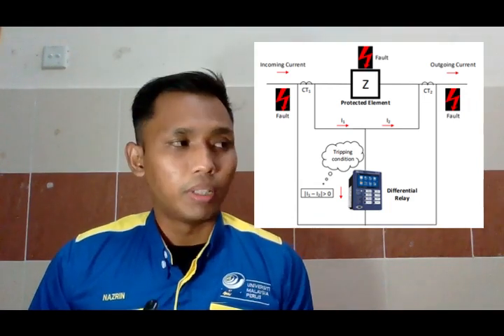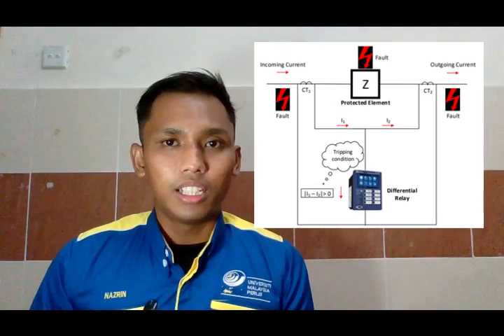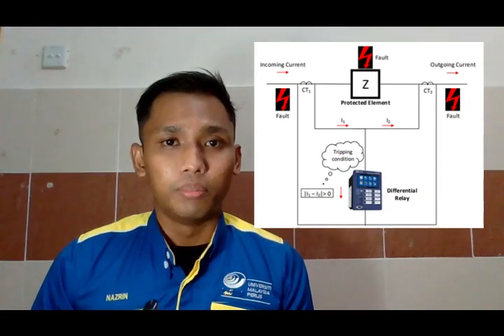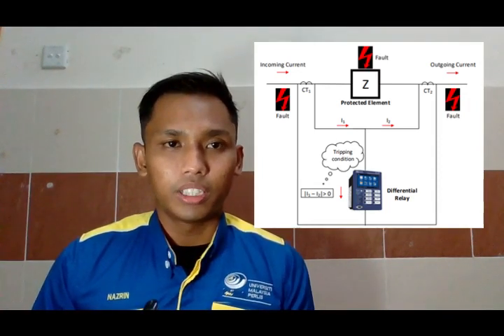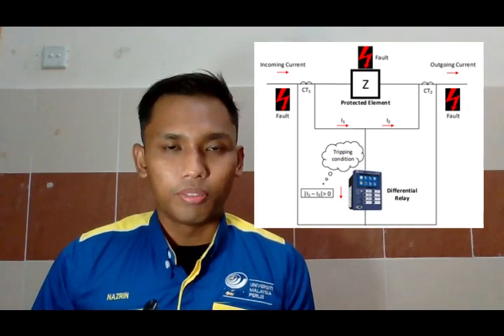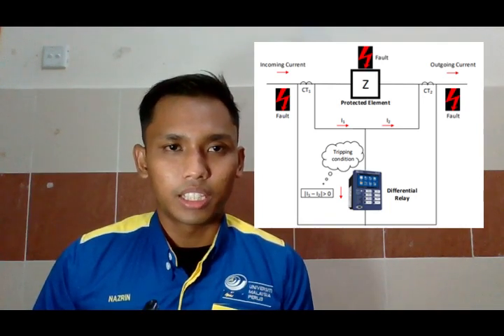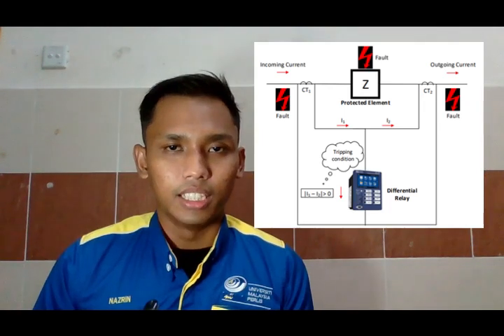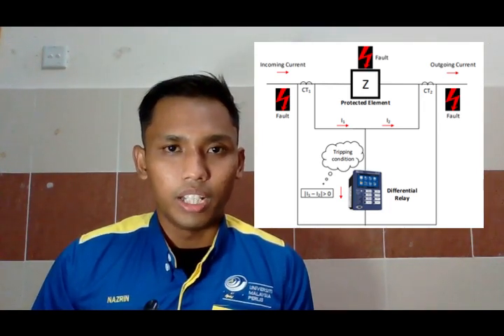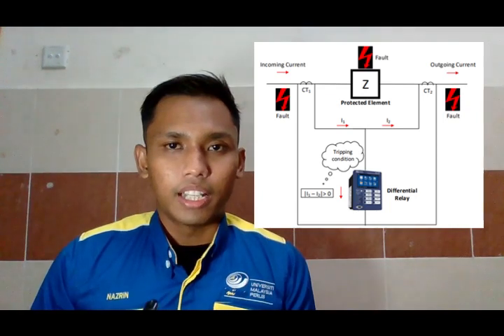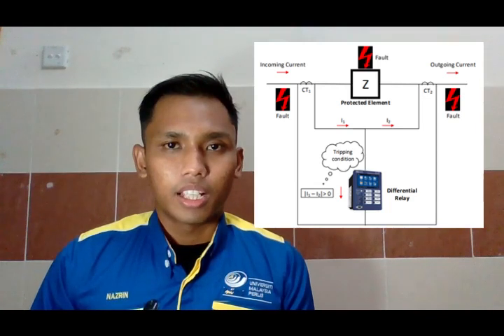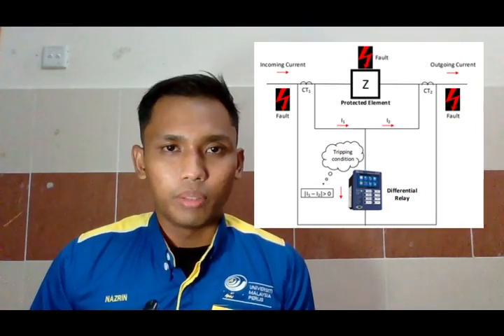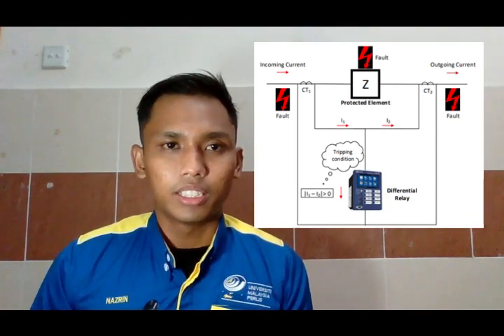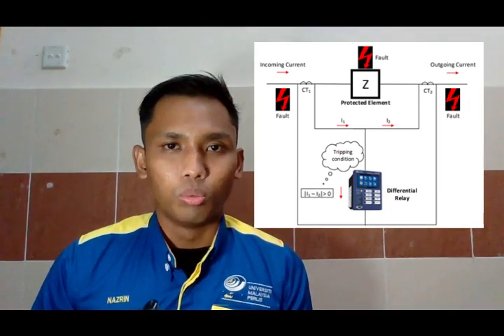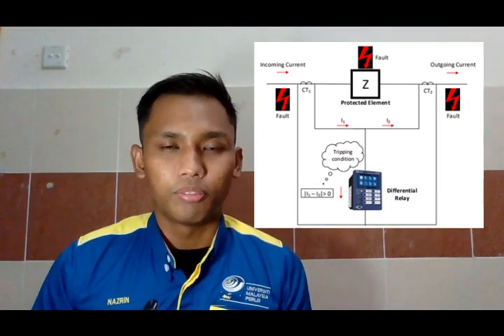As shown in the schematic diagram, a differential relay detects faults by comparing the measured currents at different locations in the network. If the difference between the measured currents on two sides exceeds a certain threshold, the relay will activate, indicating that an internal fault has occurred. Otherwise, it will not operate. As a result, the relay would trip the corresponding circuit breakers, and thereafter the circuit breakers would isolate the fault section until the fault is cleared.